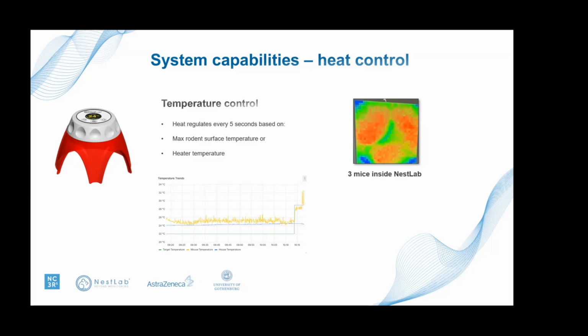So the surface temperature will be typically 33 degrees of a mice. And we can then adjust the heater based on the actual temperature of the rodent. So that's important for us to be able to control this. We do this every 5 seconds. And of course, all the sensor data we can then also read out and we can see the response.